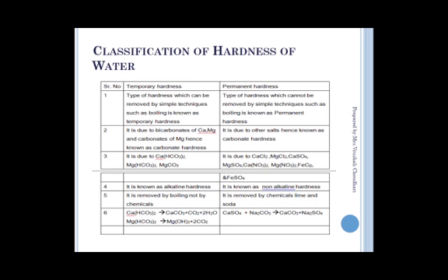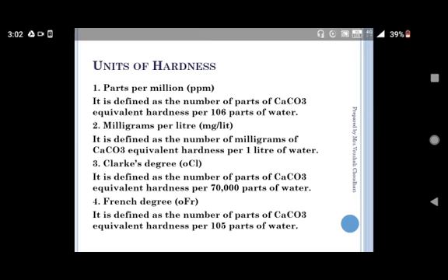Temporary hardness is also called alkaline hardness. Permanent hardness is called non-alkaline hardness. The primary technique to remove temporary hardness is the boiling process, while permanent hardness is removed by complex chemical processes like the soda lime process, zeolite process, and ion exchange process.